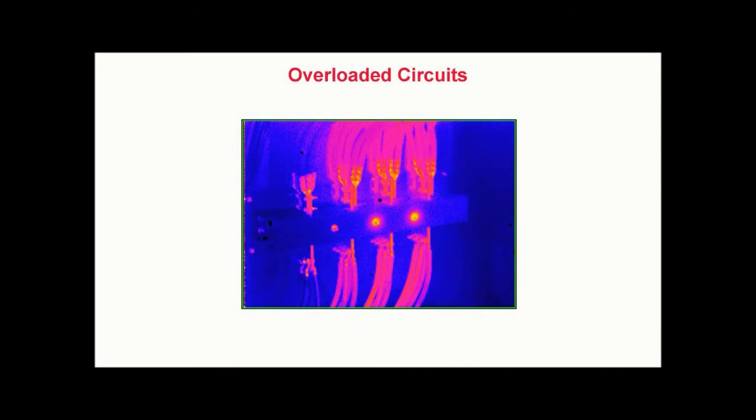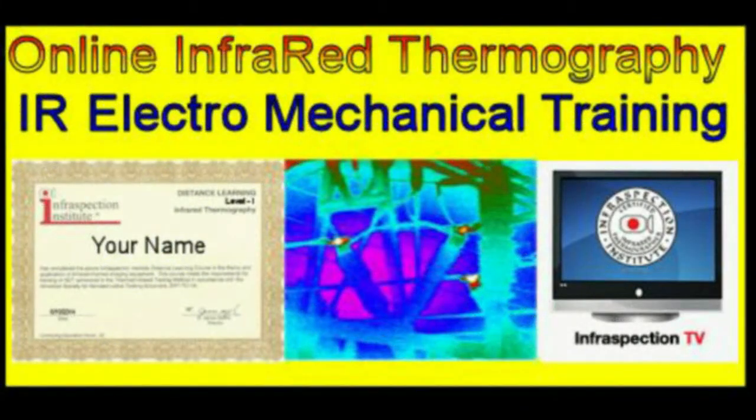This image was captured during a quality assurance inspection of a new emergency generator system where the installed conductors were found to be undersized for the circuit load.